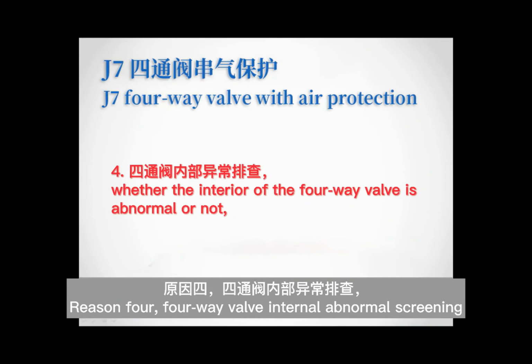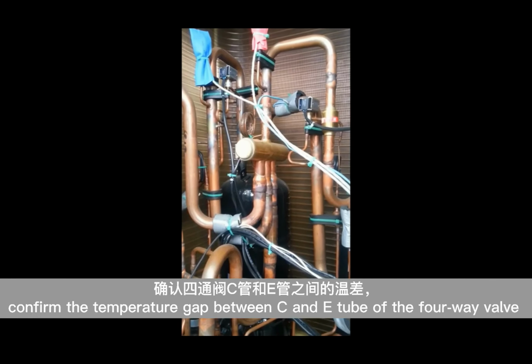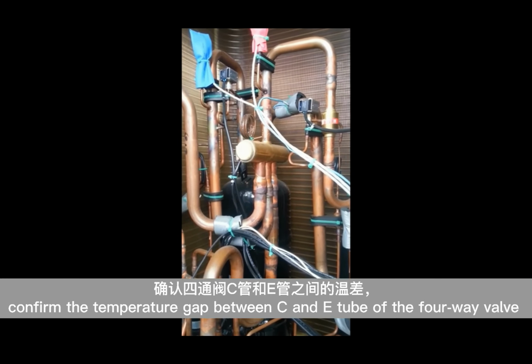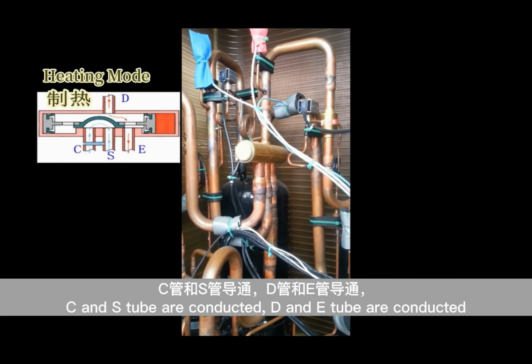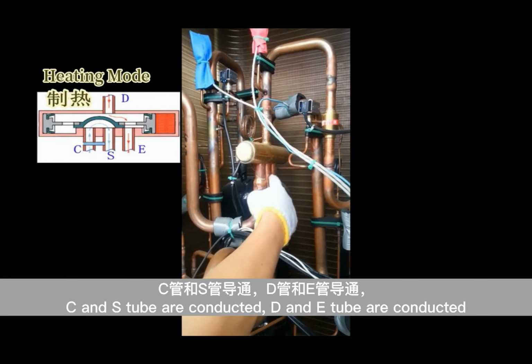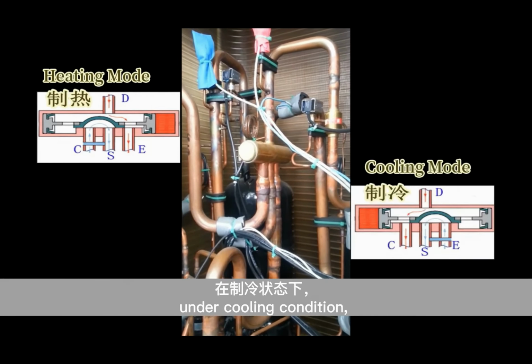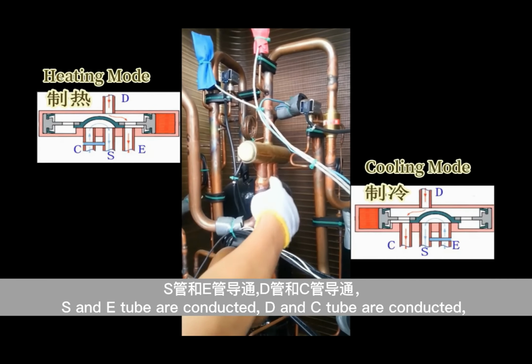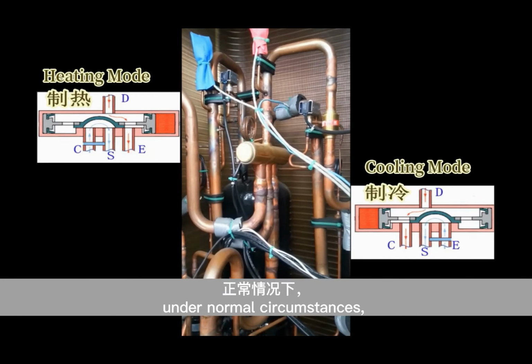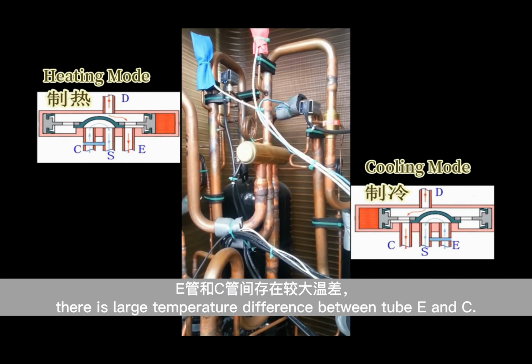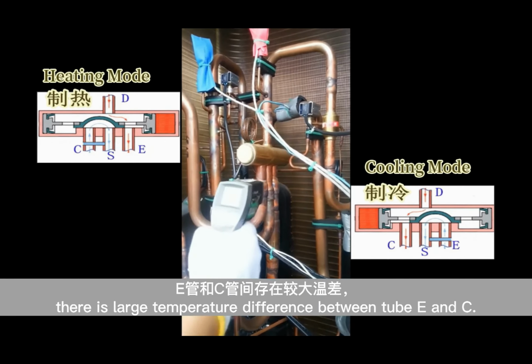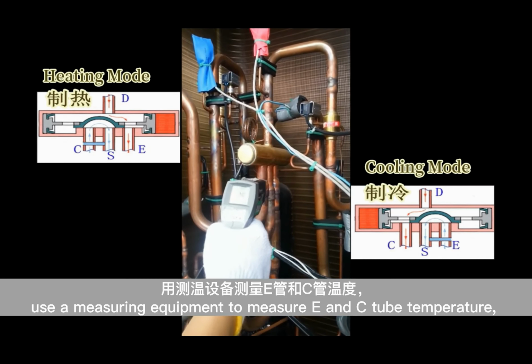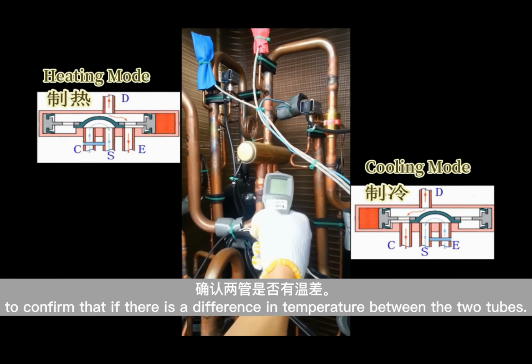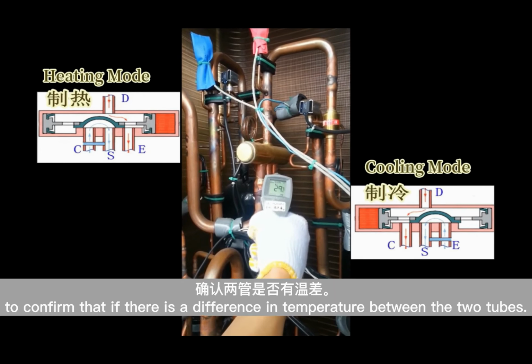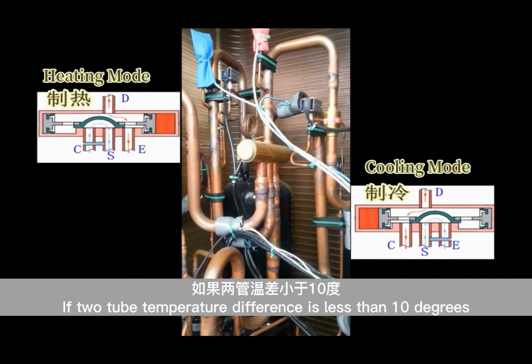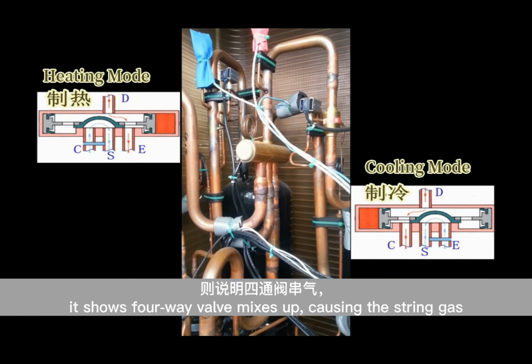Reason 4. Four-way valve internal abnormality screening. Confirm the temperature gap between the C and E tube of the four-way valve. Under heating condition, C and S tube are conducted, D and E tube are conducted. Under cooling condition, S and E tube are conducted, D and C tube are conducted. Under normal circumstances, there is a large temperature difference between tube E and C. Use a measuring device to measure E and C tube temperature, to confirm whether there is a difference in temperature between the two tubes.